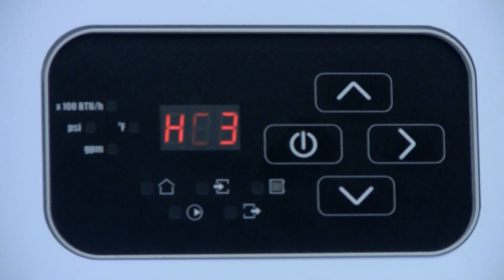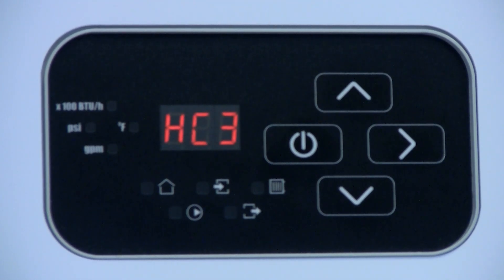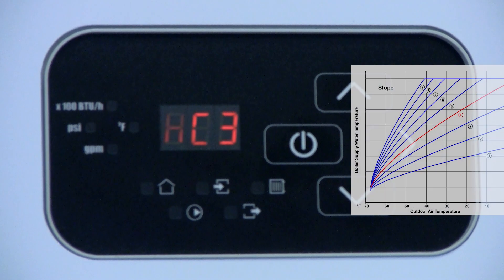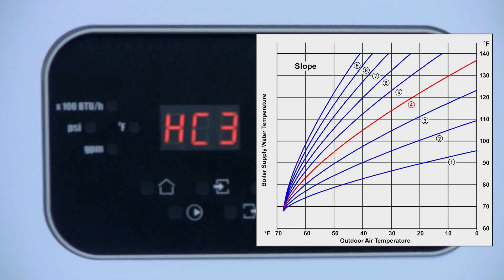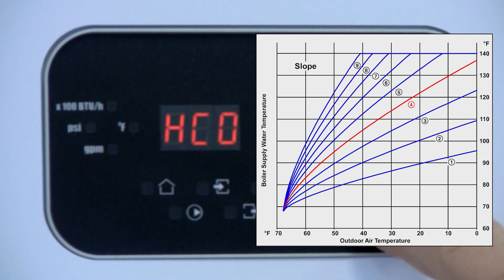The following two parameters are related to setting the heating curve for weather compensated operation using an outdoor temperature sensor. The slope parameter can be set between 0 and 9 and adjusts the design day temperature set point. The factory default setting is 4.